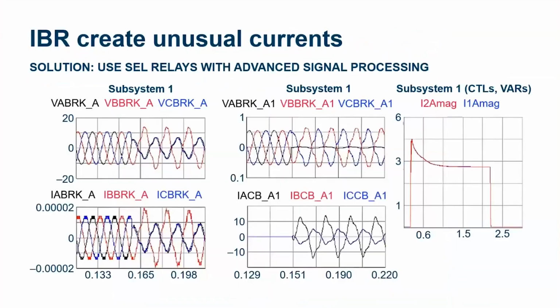Inverter-based resources create very unusual currents, unusual from the perspective of history. Since Nikola Tesla designed the AC synchronous generator, those waveforms have been well described mathematically for engineers. Inverters don't follow those rules. Inverters can follow the rules of the software coding chosen by the day. And the firmware that's in those inverters is subject to a lot of human error.